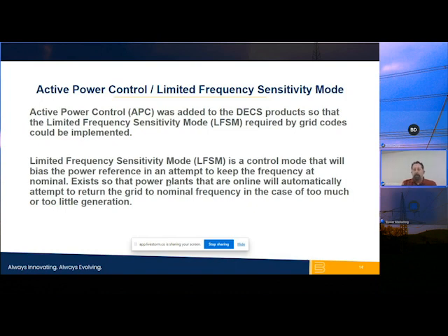So we're taking all that data that we monitor, and based upon that data, we can do the active power control, or if we get outside of our limits, we can do the limited frequency sensitivity mode control by sending out signals to devices that are doing that control. So we could bias the governor controls. We could send raise and lower signals out to the devices that are in direct control of the frequency. So we'll increase kW, which essentially is going to increase the frequency, or decrease kW, which is going to decrease the frequency. So active power control is really when we're at the nominal mode, and when we get outside of our limits, that's when the device would change to the limited frequency sensitivity mode of operation.